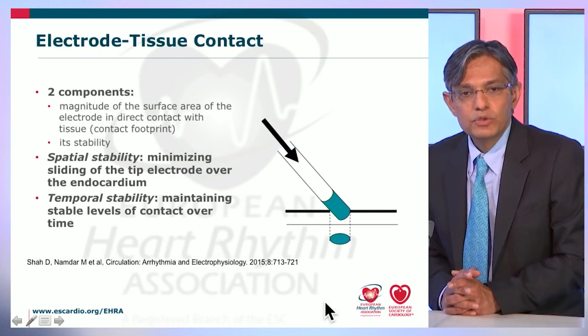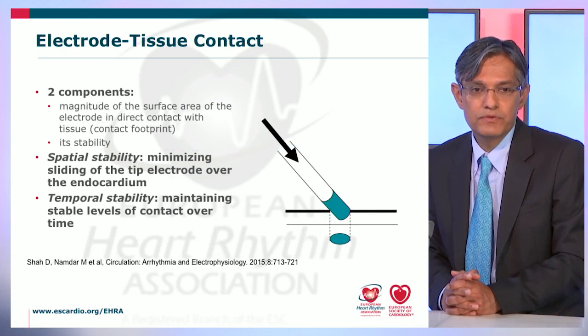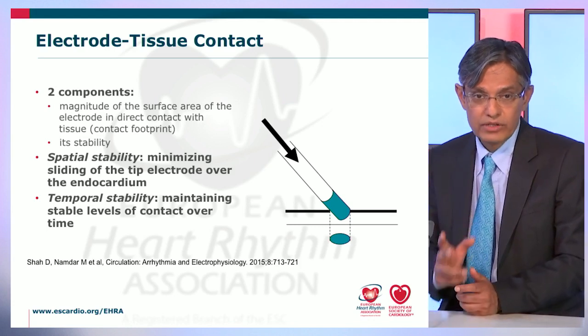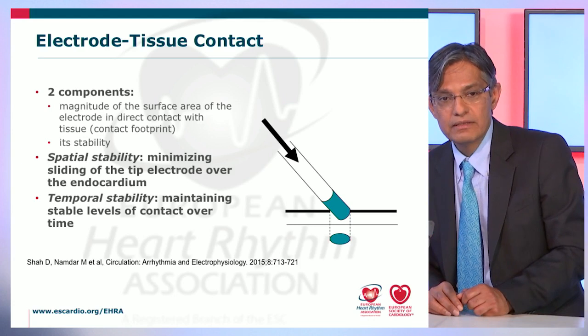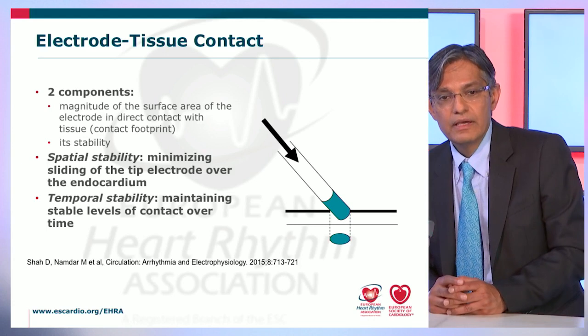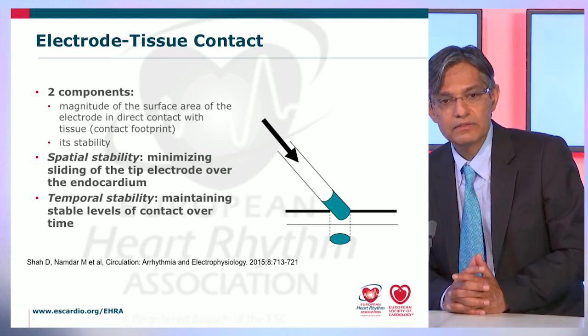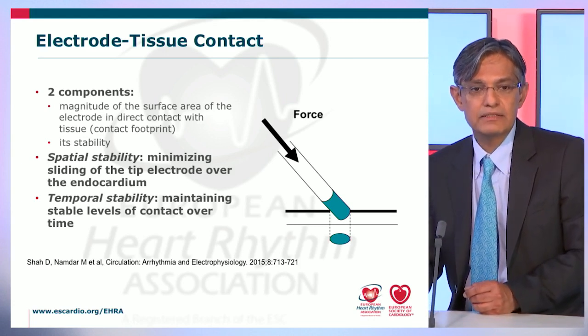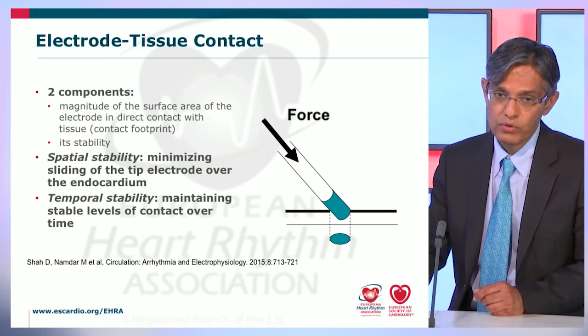If you look at electrode tissue contact conceptually, one can think of it as being made up of two components: the magnitude of the surface area of the electrode in direct contact with the tissue — the so-called contact footprint — and its stability. That stability can be considered in two ways: spatial stability, such as minimizing sliding of the tip electrode over the endocardium, or temporal stability, maintaining stable levels of contact over time. Both of these are very important.